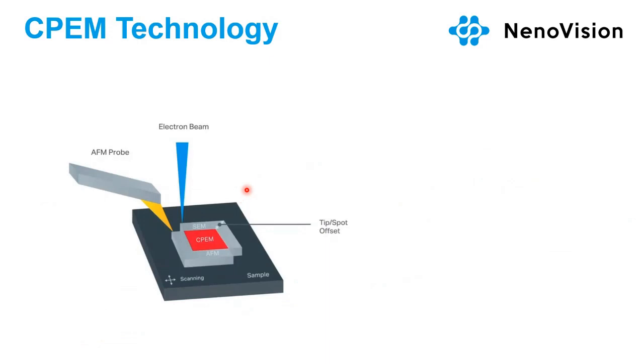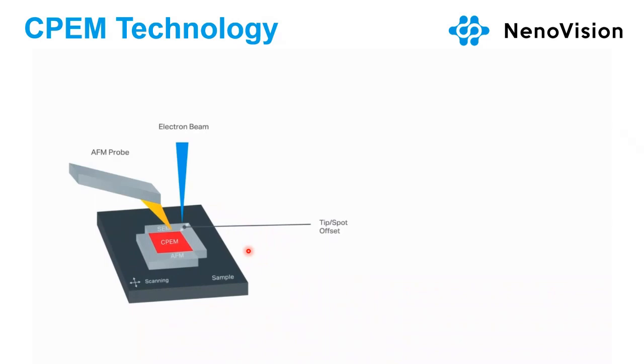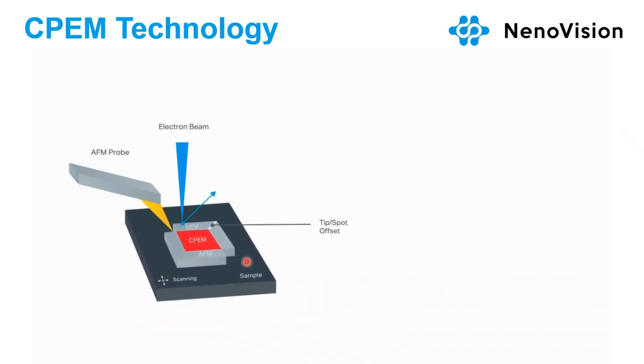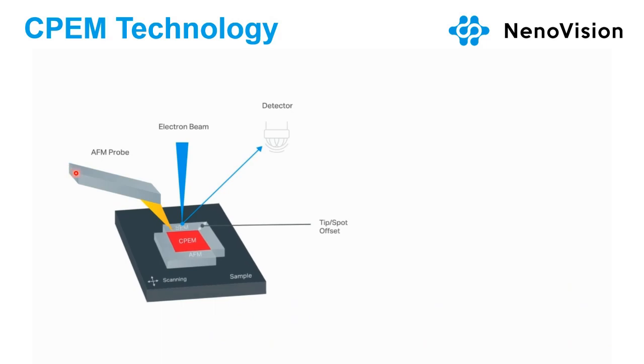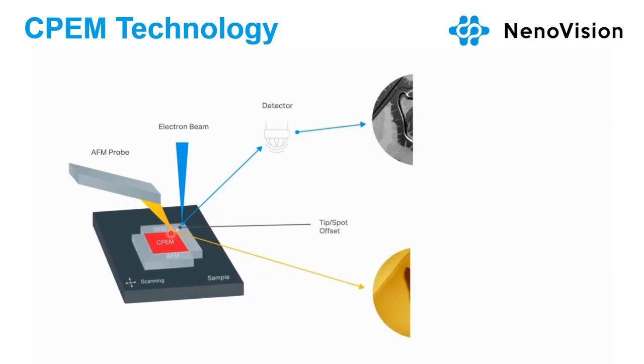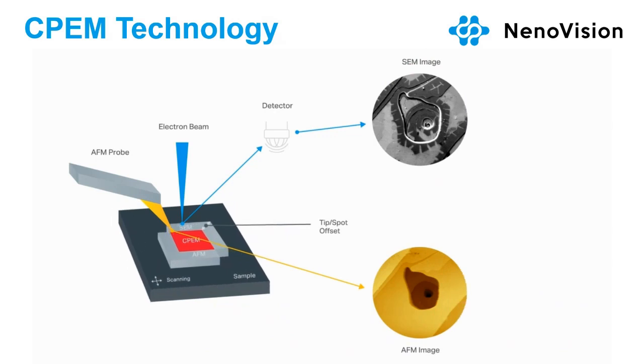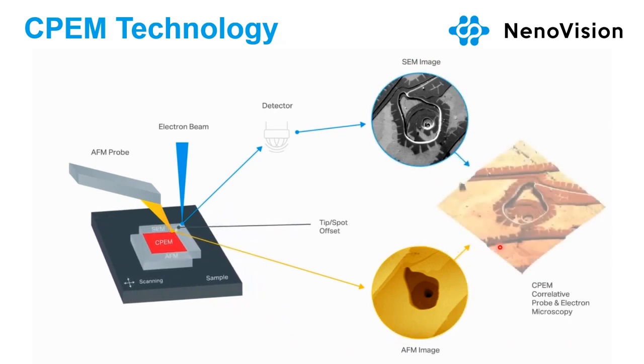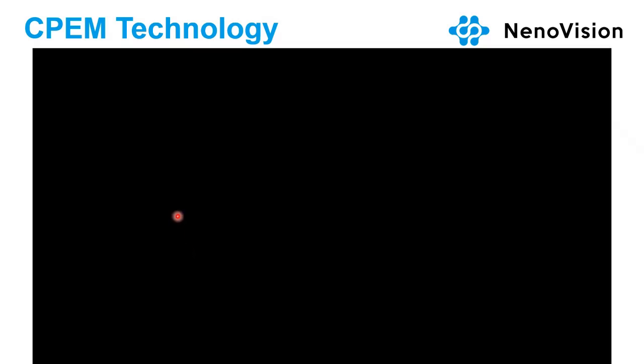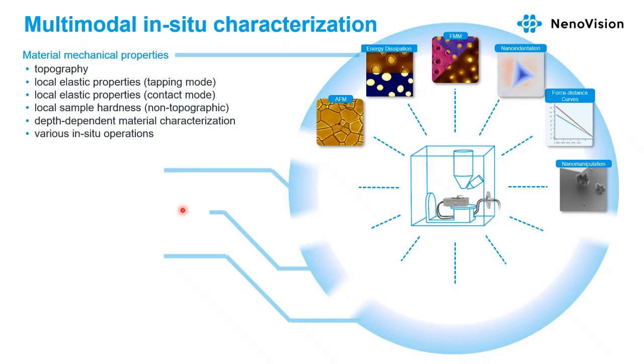But how? I have a scheme here showing the probe and the electron beam. They are close to each other, and we have the electron beam focused to one point. And so we are scanning, moving with the sample, analyzing simultaneously both of these signals. So we get the SEM, we get the AFM topography image. At the same time, we post-process that, we get rid of the offset, and we have the three-dimensional image.